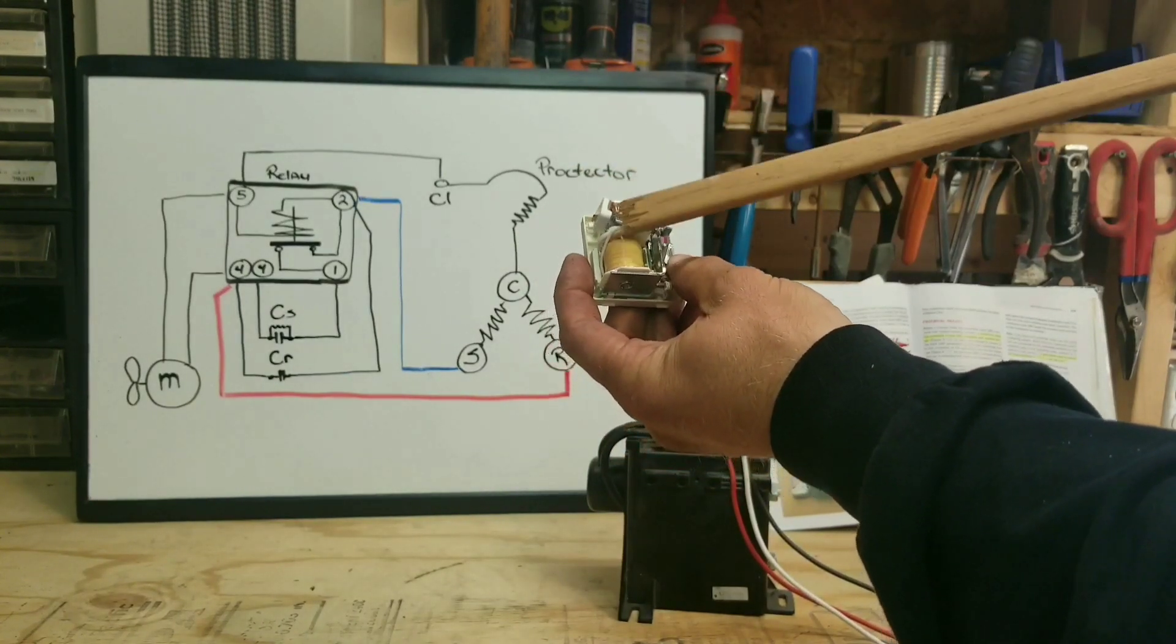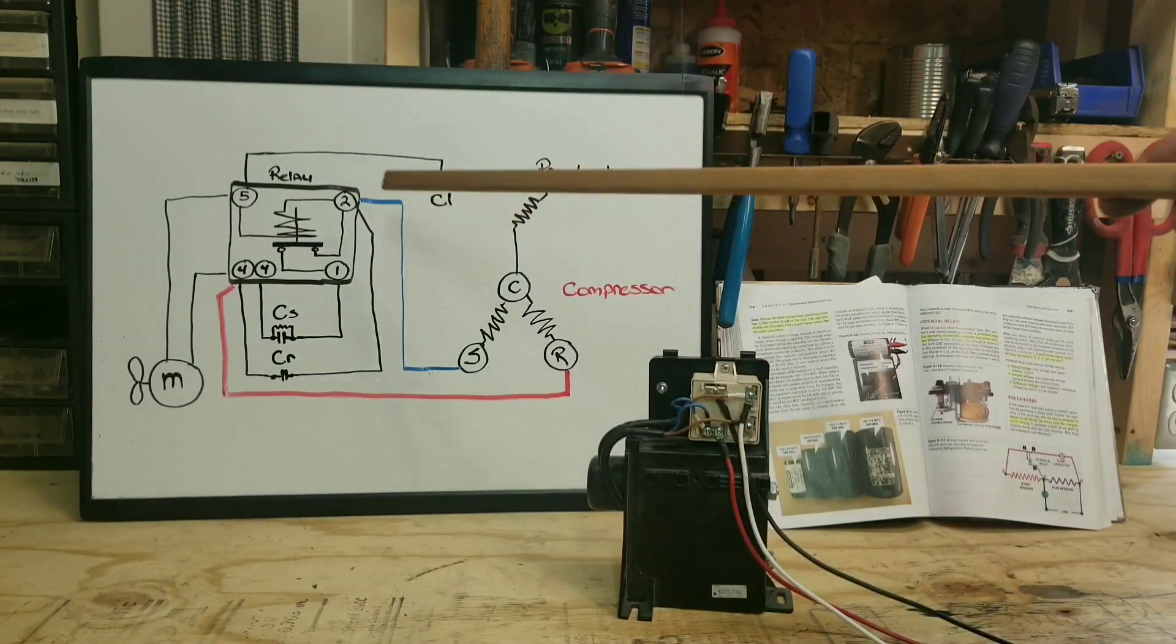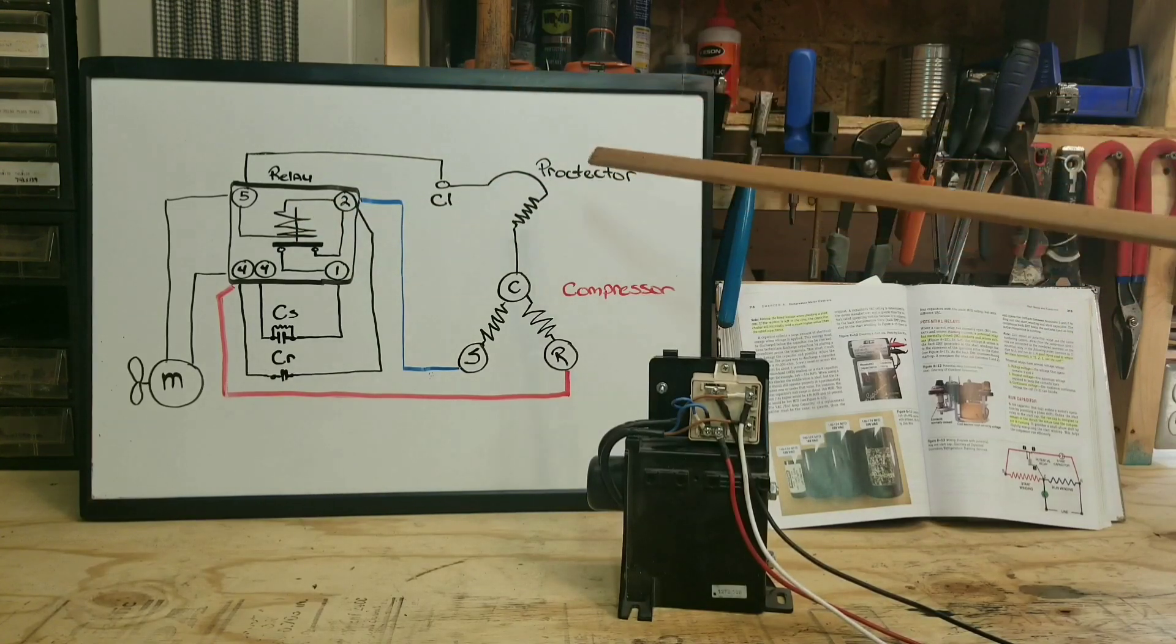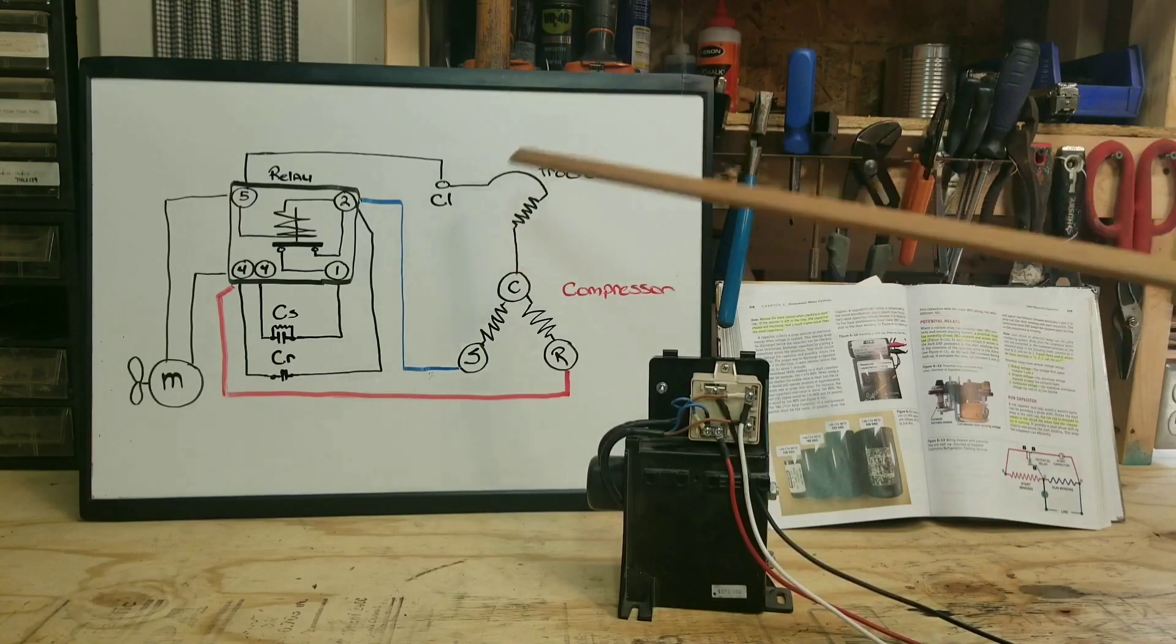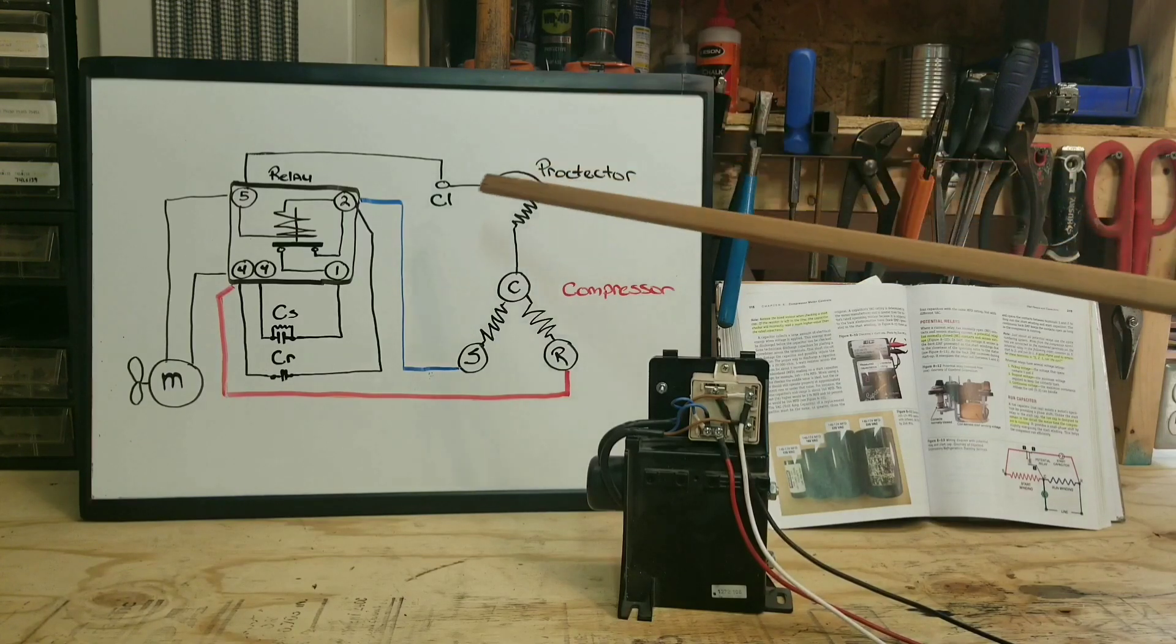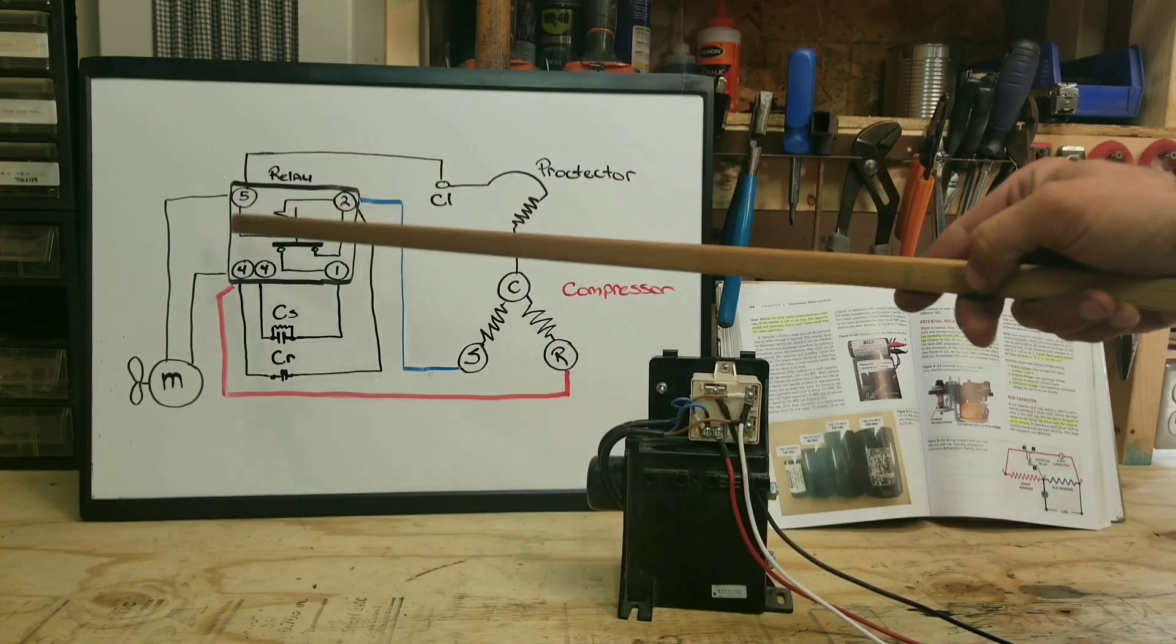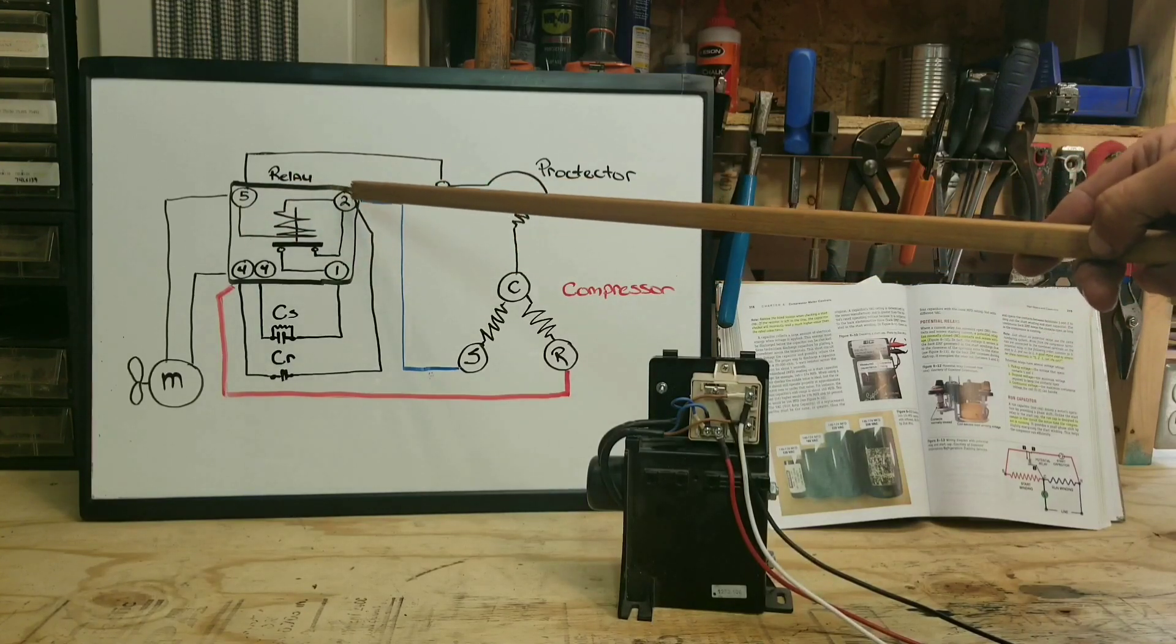Now also, you can check because sometimes they could fail open. It might—your compressor might start or it might struggle to start but eventually start. It might make a lot of noise, might be pulling a lot of amps, maybe cycling off on your thermal protector. You can check across two and one. If it's unplugged and it's in the off position, this will be, assuming it's working properly, this will be normally closed. So you can check across one and two and you should have continuity through there.